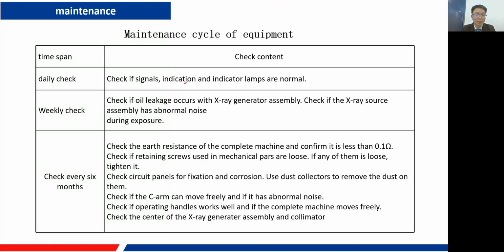And in weekly check, we need to check the oil leakage occurs with X-ray tool. Check the X-ray source assembly has abnormal noise during the expose. In every 6 months, we need to check the earth resistance of the complete machine and confirm it's less than 0.1 ohm. We also need to check the power supply is 220 and the zero ground voltage is less than 5 volt.